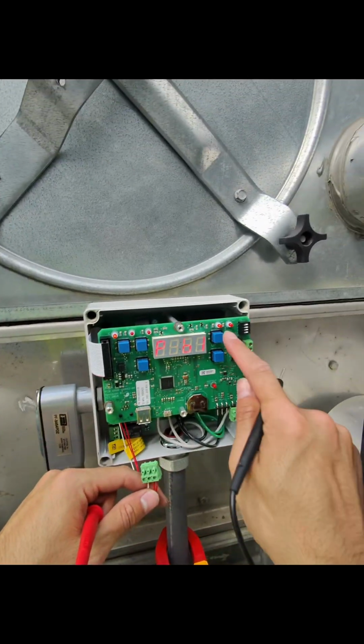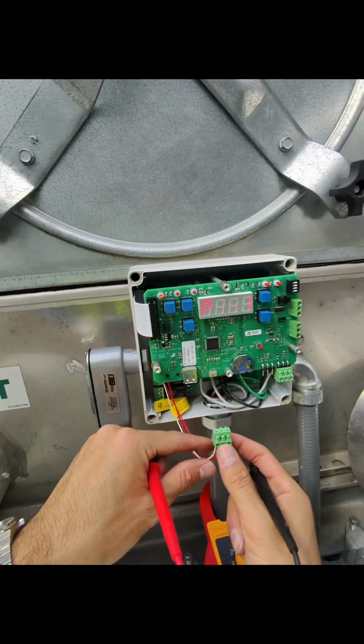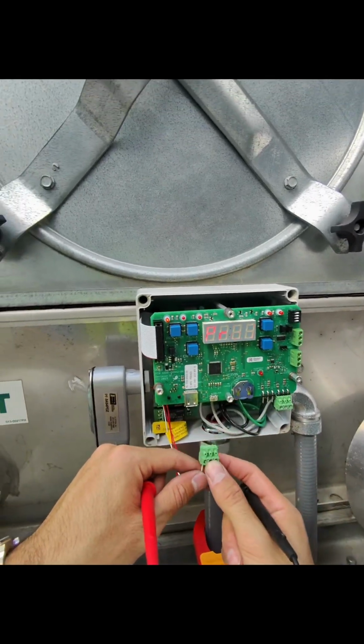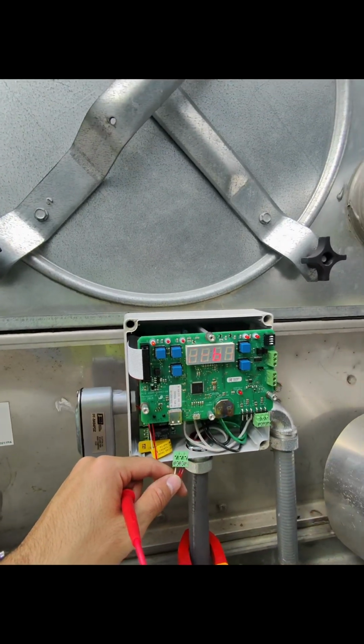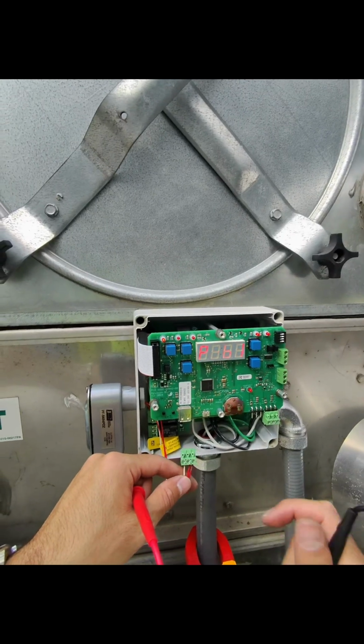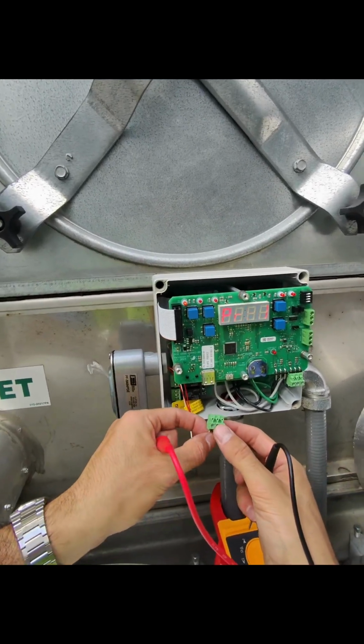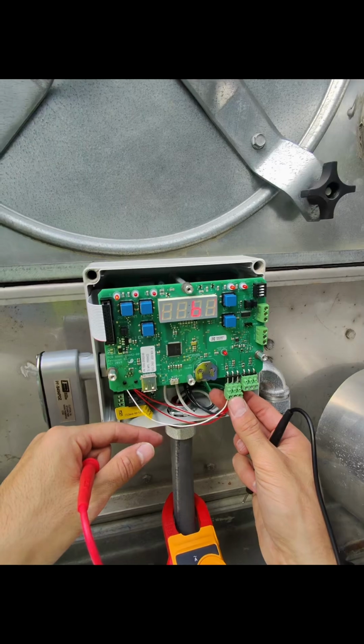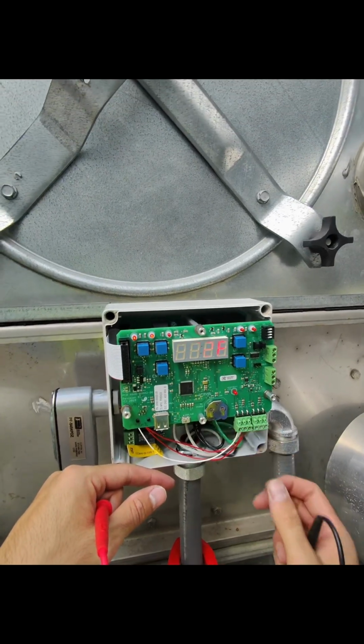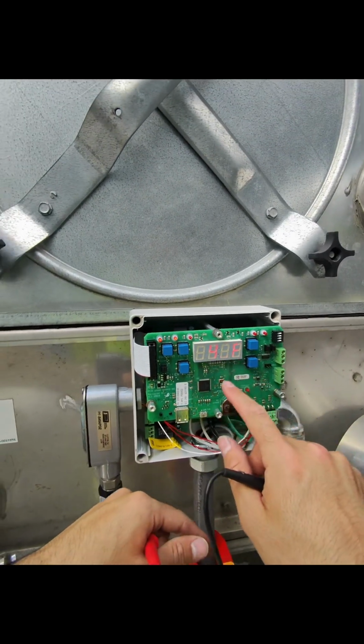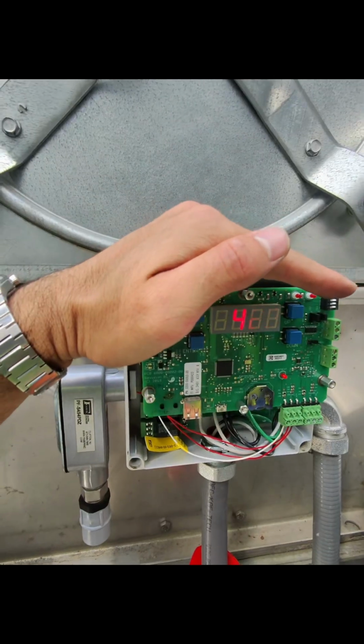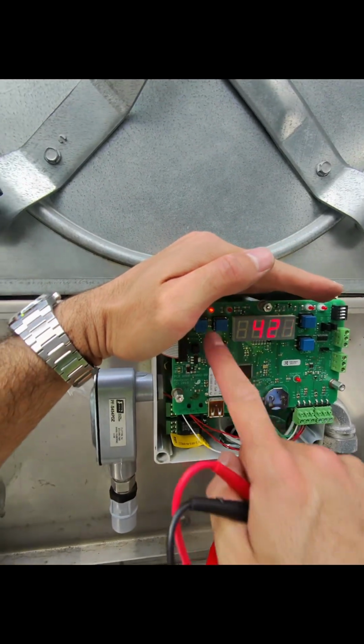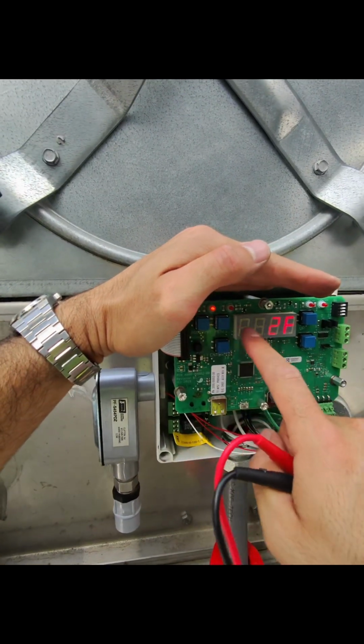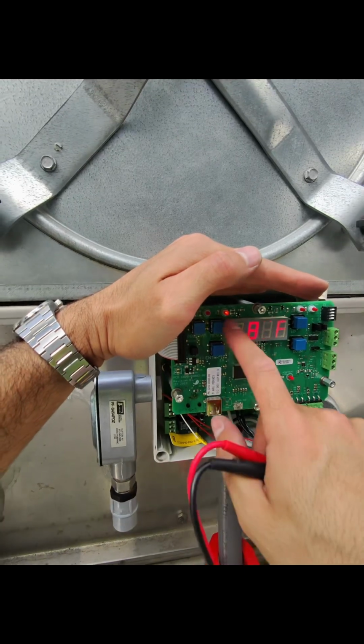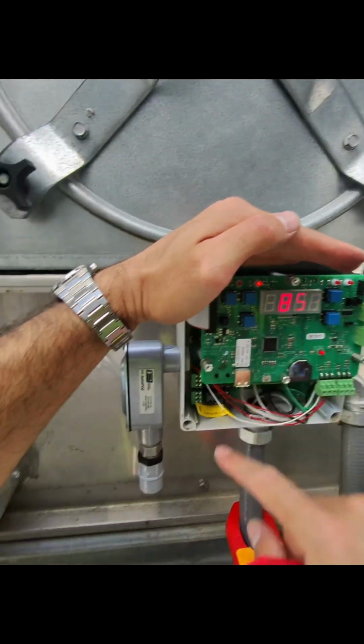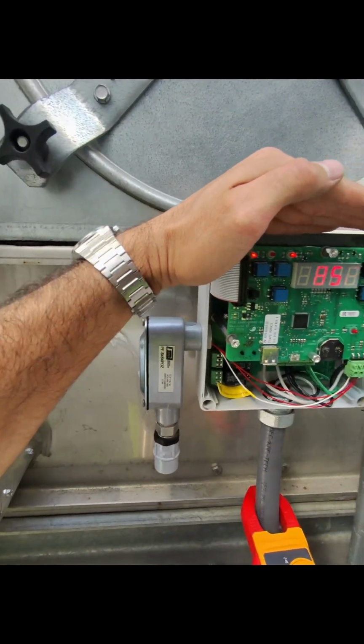You can see the panel went into an alarm when I pulled the probe out. That's just a normal probe alarm. The heat trace will run on 100% output when the probe is disconnected or the controller detects an open probe or shorted probe. As soon as I plug it back in, the probe alarm clears. You can see our set temp here is 42 degrees Fahrenheit. It indicates it's displaying the set temperature right now. And now it switches to actual temp, 85F, which is what the ambient sensing RTD is detecting.